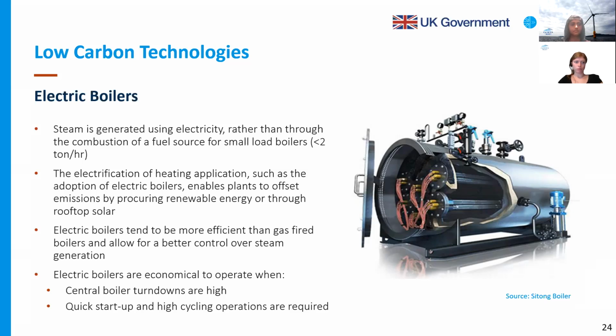Yeah, electric boilers tend to be more efficient than gas-fired boilers, and they allow better control over steam generation. And they tend to be easier and cheaper to maintain, so nothing beyond your minimal routine inspections is required. But of course, as with any other boiler, they do require scale control measures. You do require periodic blowdowns to maintain your efficiency and prevent accumulation of TDS.